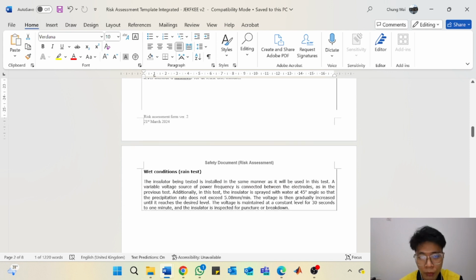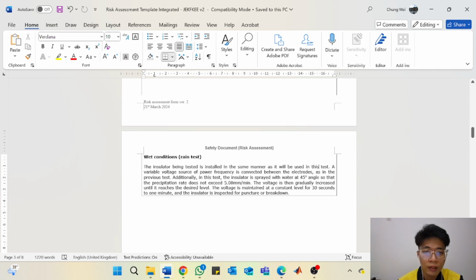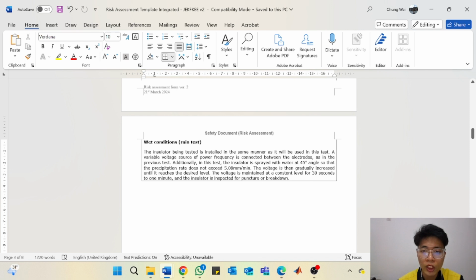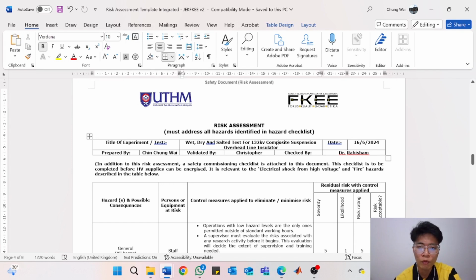Whereas for the wet condition, rain test, the insulator being tested is installed in the same manner as it will be used in this test. A variable voltage source of power frequency is connected between the electrodes as in the previous test. Additionally, in this test, the insulator is sprayed with water at 45 degrees so that the precipitation rate does not exceed 5.08 mm per minute. The voltage is then gradually increased until it reaches the desired level. The voltage is maintained at a constant level for 30 seconds to 1 minute, and the insulator is inspected for puncture or breakdown. Before we conduct an experiment, we need to perform risk assessment.